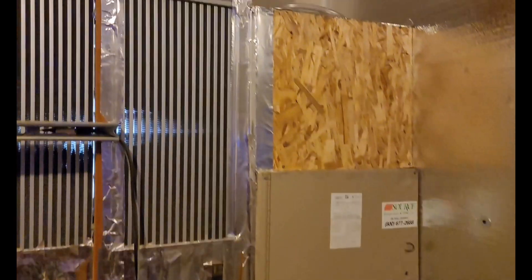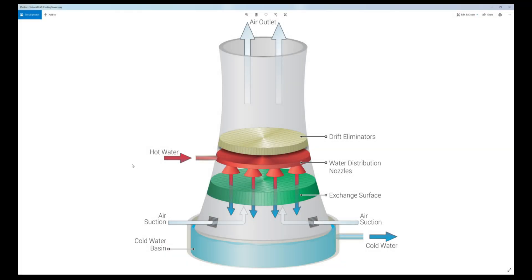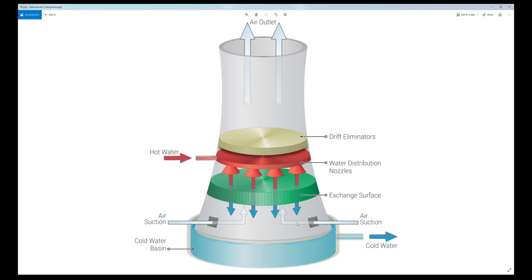Just to kind of recap a little bit on the water cooling tower that we've got going on, the hot water from the mining room would be going into here and we're using spray jet nozzles to spray the water coming in over the radiator on the bottom. While that's going on there is air interacting with the water that is going downward and causing it to evaporate, and it's actually causing the water to cool down and all the heat will be going upward.